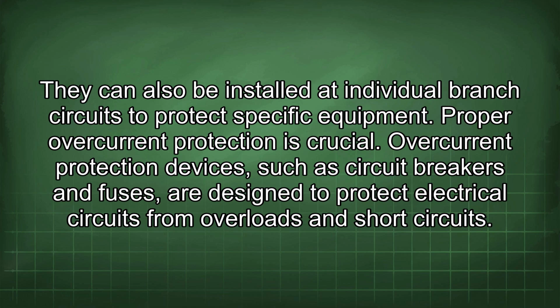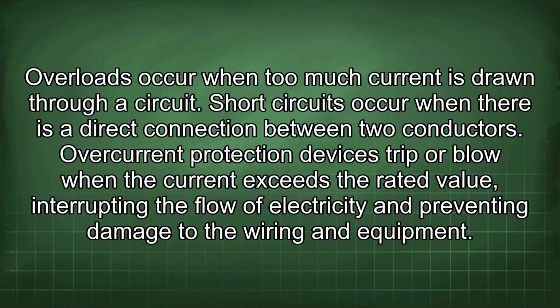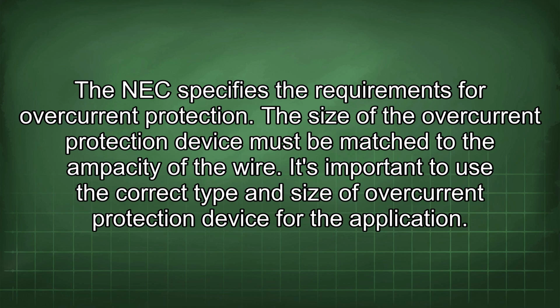Proper overcurrent protection is crucial. Overcurrent protection devices, such as circuit breakers and fuses, are designed to protect electrical circuits from overloads and short circuits. Overloads occur when too much current is drawn through a circuit. Short circuits occur when there is a direct connection between two conductors. Overcurrent protection devices trip or blow when the current exceeds the rated value, interrupting the flow of electricity and preventing damage to the wiring and equipment. The NEC specifies the requirements for overcurrent protection. The size of the overcurrent protection device must be matched to the ampacity of the wire. It's important to use the correct type and size of overcurrent protection device for the application.